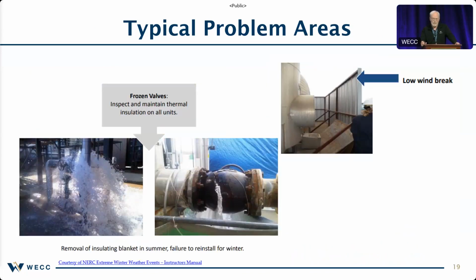This one here, the frozen valves, that talks more to what we might see here in WECC in the southern areas. We're designing the power plants to operate during the heat of the summer because that's when our peak is. And so in the wintertime, they put insulating blankets over the valves to make sure that they're okay, but they took them off during the summertime and didn't replace them. And then when the cold weather moved in, we have broken valves.